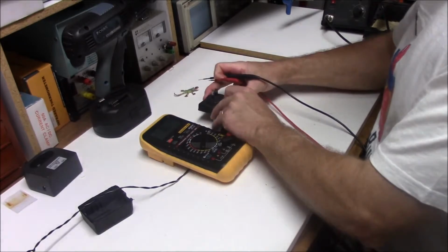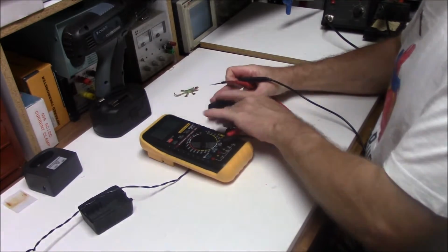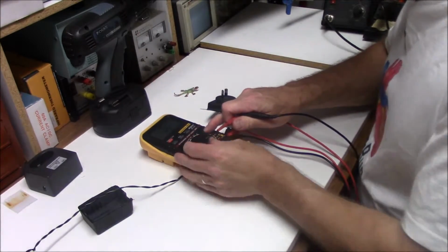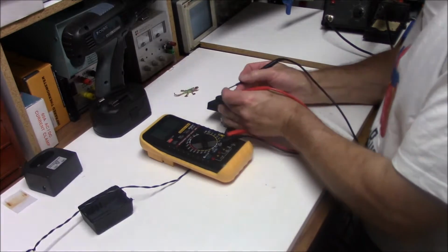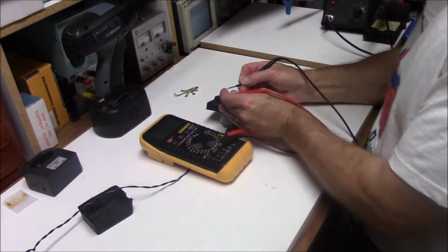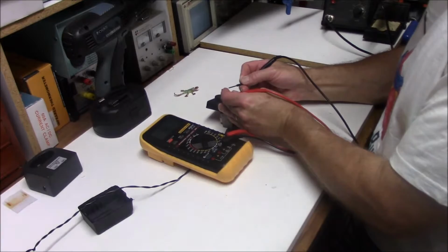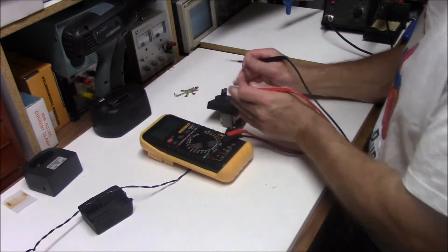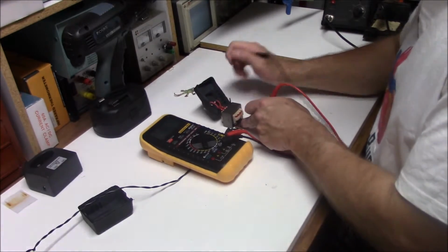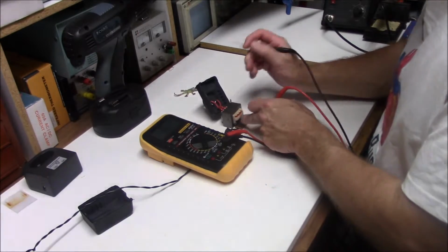And this is the part that goes into the power point. So we need to put that on our ohm rating there, as you can see, and then we just check this and this. As you can see, there's no continuity there. So that tells me that there must be a break in the primary winding through here.